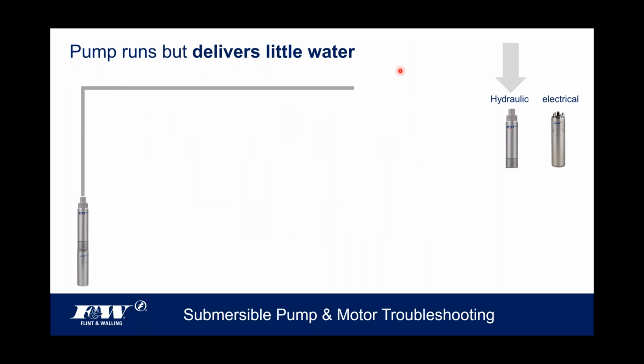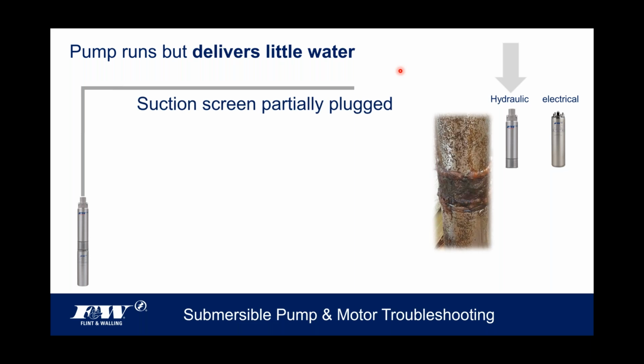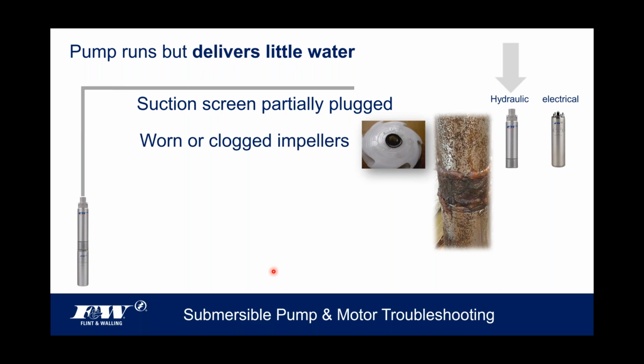Here's the problem. The pump runs, let's say it runs okay, and it shuts off. It's just not delivering a lot of water, very little water. One reason might be the suction screen, which is located right around the motor mount where the pump and motor come together, where that marriage takes place. It's typically a plastic or stainless steel mesh screen, but if that gets plugged up because the water quality in that well is horrible, with lots and lots of iron and all kinds of things, then everything north of that is going to be slowed way down, barely able to pull water through there. So that might be a situation that would cause it to deliver too little water.